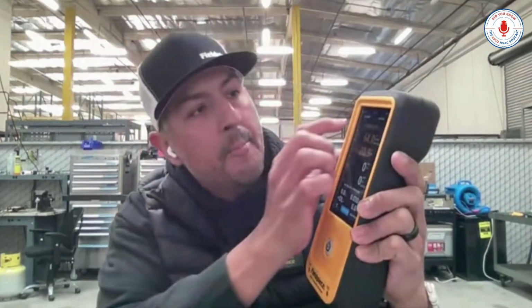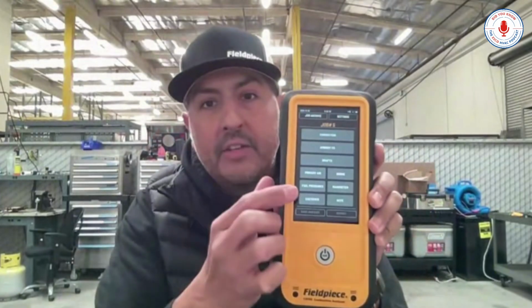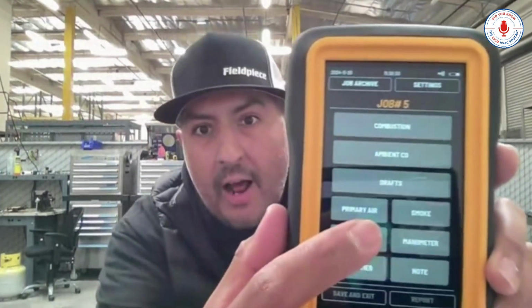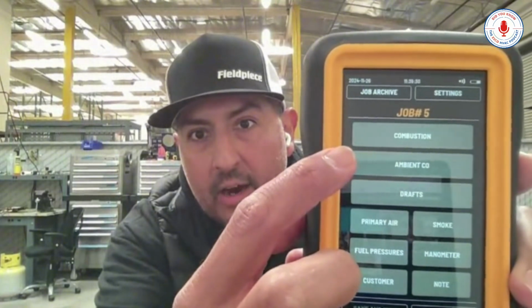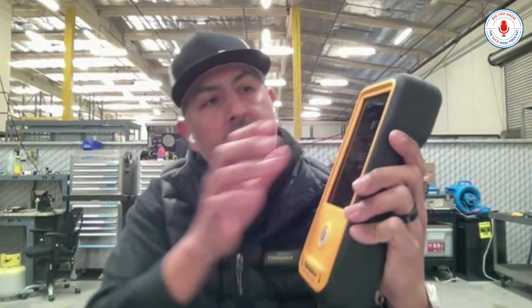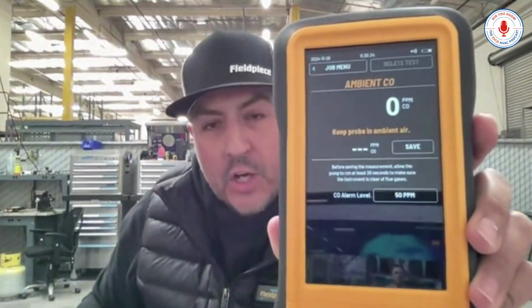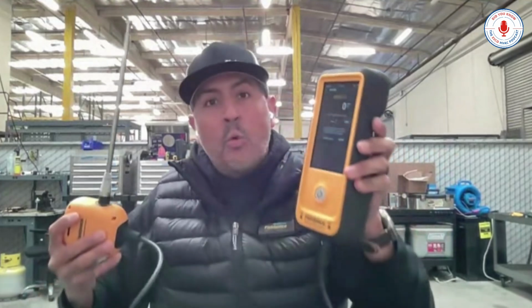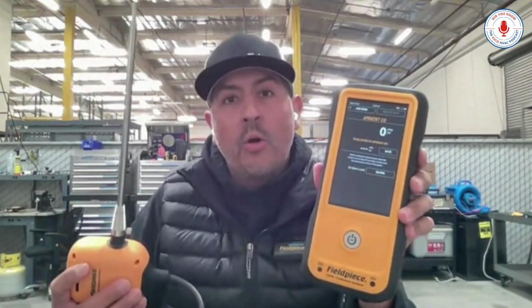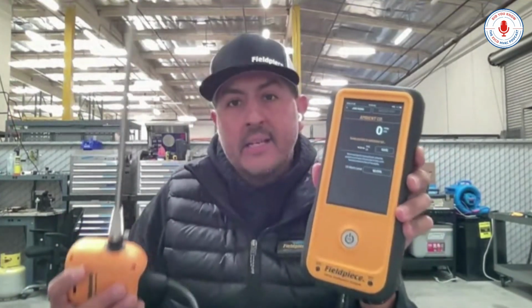Now, on the Fieldpiece combustion analyzer, this is your typical combustion screen where you see a bunch of measurements. But you can go back to the job menu, and whether you see it or not, there's another button that says ambient CO. So I'm going to press on that ambient CO, and now you just get carbon monoxide on your screen. And you can very casually, without alerting your customer, just walk through the building, heading towards the appliance under test, and just have this in your hand and monitor what the CO levels are, right?